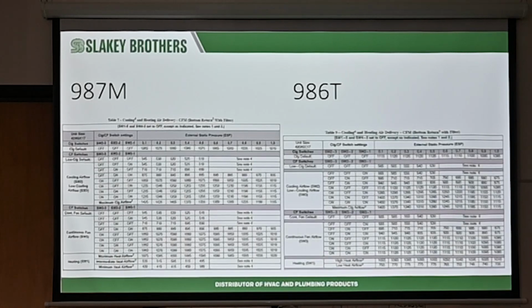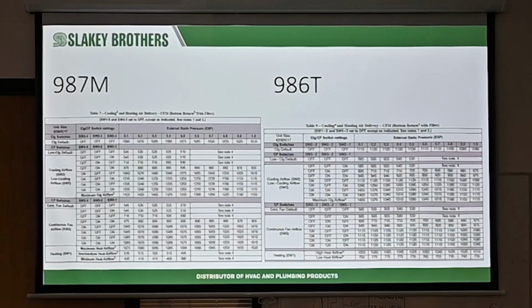You got your coil sitting right here. Supply's gonna be right up there. A lot of people make the mistake and they go return, supply, that's my static. Oh, perfect. I got 0.4 static. Look at my airflow. I got 1,255 CFM or whatever it is. I'm good to go. I got what I need. But these numbers are external static of the furnace. So now the challenge is you got to figure out how to get in here on this evolution unit.